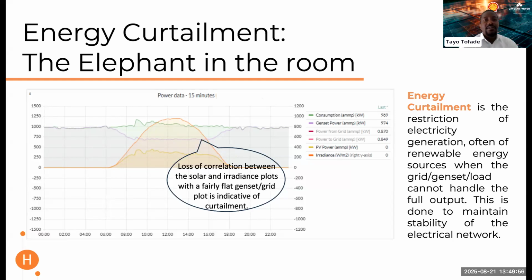From a grid perspective, if you're injecting too much there's congestion on the grid, and there's direct communication from the grid operator saying we need curtailment on this solar. From a genset perspective, it's acknowledging the base load of the genset, the minimum required load for it to operate efficiently. From the load side, it could be economic impact on the operations of the plant, but we'll go into all of that in detail.